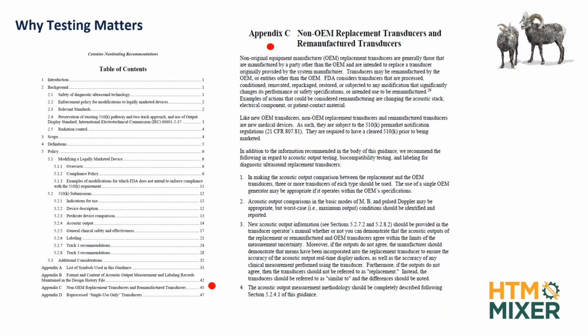So we do that at our facility for companies, OEMs who are looking to get their ultrasound system in the market. We're the company that does the acoustic power testing for them for that submission. But it said, if you're going to change the acoustic stack, you need to make acoustic output comparisons between the replacement you're going to put in there and the OEM. You've got to do at least three of them to show statistics. Okay, and you just can't.